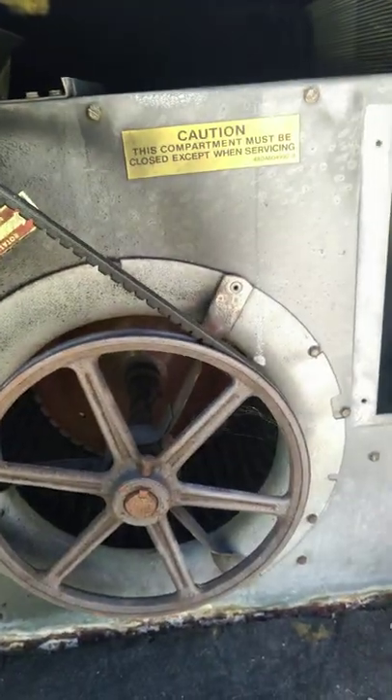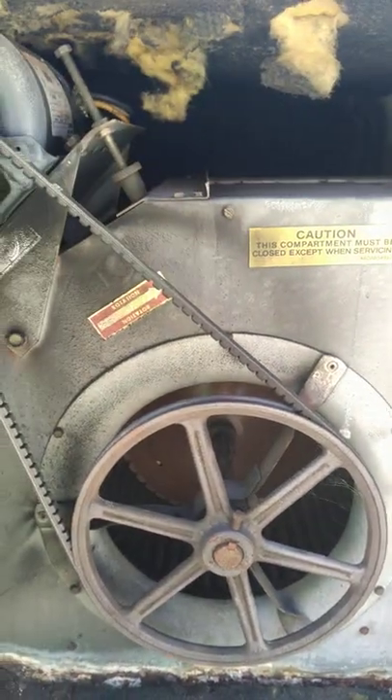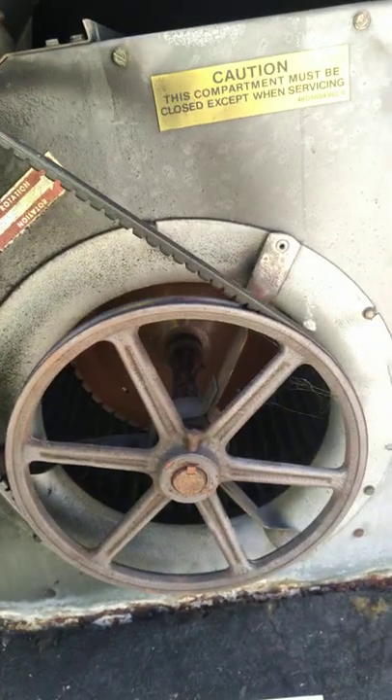I've never been on this unit before. Saw it the other day — it froze up. It's low on gas and we can't get the charge right. So I checked the airflow and the blower is going the wrong way. It's a three-phase motor.